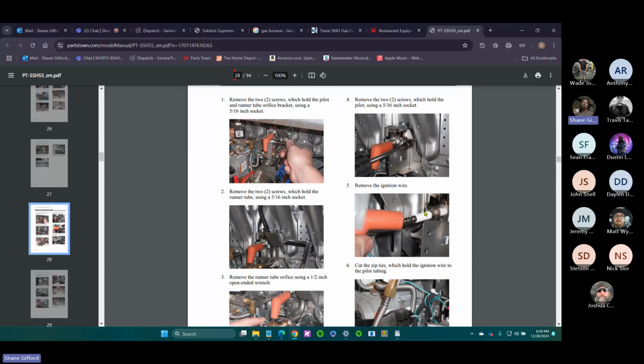Some appliances out there, and I think there was one at Shaka's in Idaho Falls, have an oven in the back room, and their pilot assembly is an electrode like this, but then they also have their thermocouple right next to it, and then their igniter. And it's like, dude, they made all three parts look the same. You're like, which one's the igniter and which one's the thermocouple? So if you're ever in that situation, it's not a bad idea to mark with a Sharpie on the little boot right here, like a 1 or a 2, and then mark an identical one on the part that you took it off of.